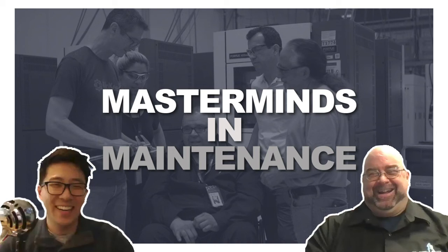So I take one set of data. With most wind turbines, I'll walk into the base of the tower, take a 1 minute set of data from the base, not have to climb. And I will have more data than at any load. It's not load dependent. I'll have more than what they get with setting the vibration data stuff up tower. That usually takes about a day a tower to run their analysis.